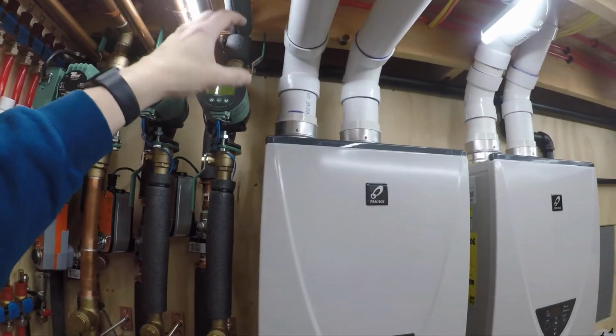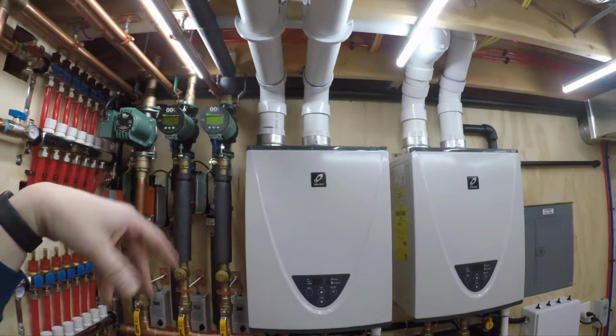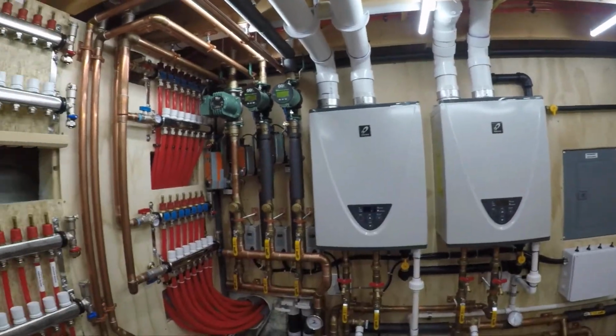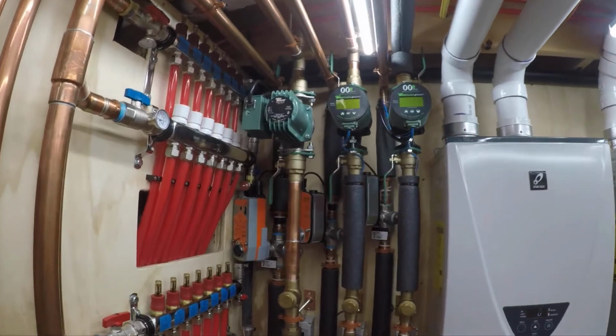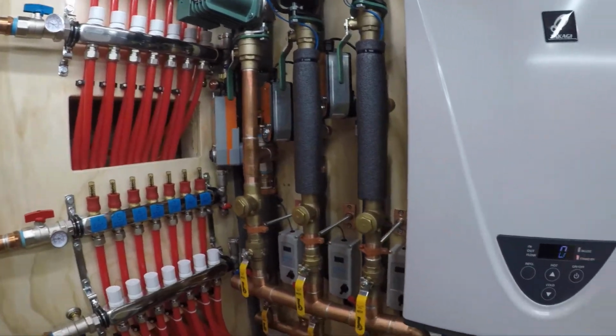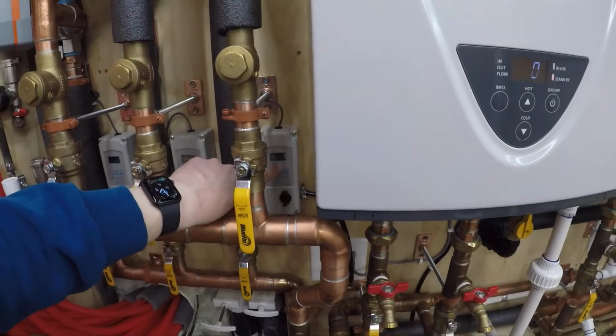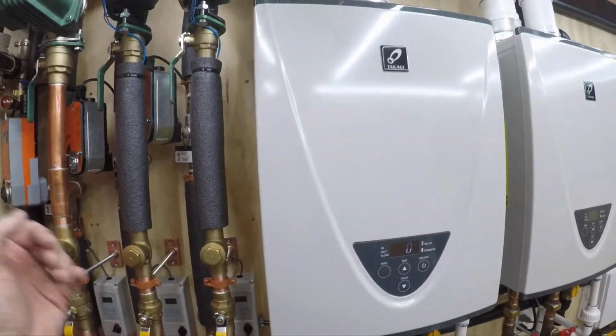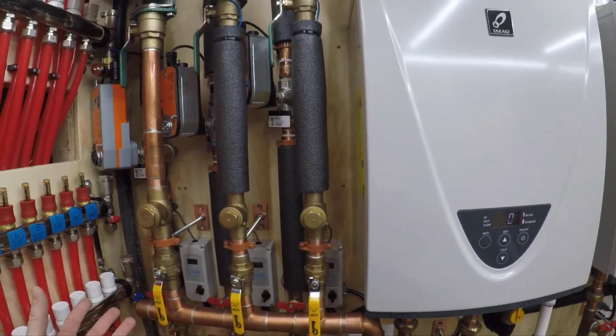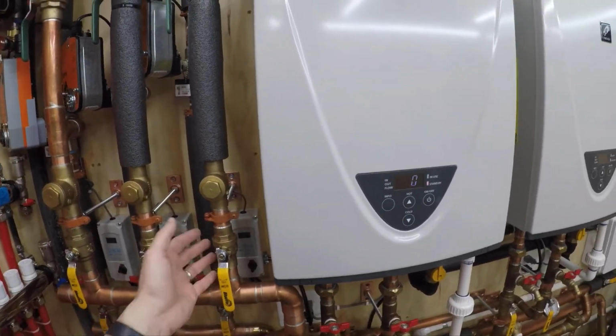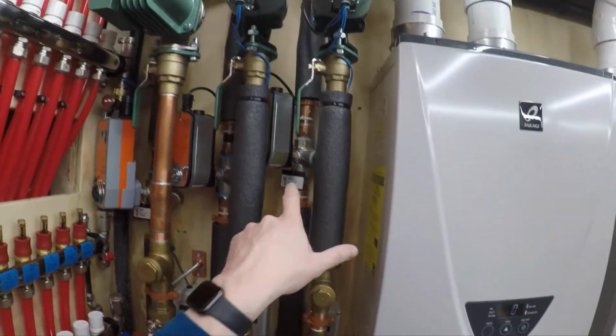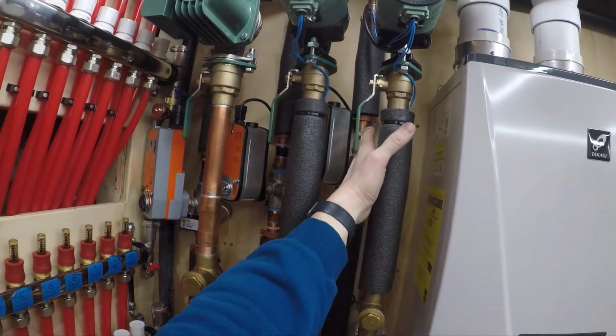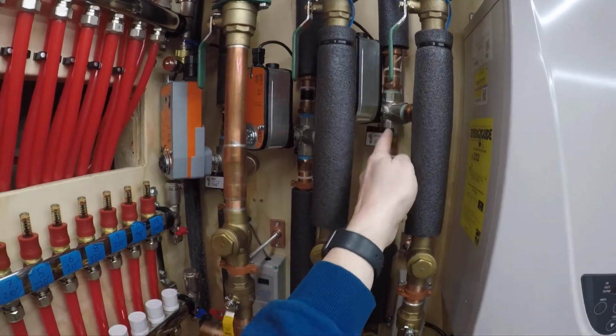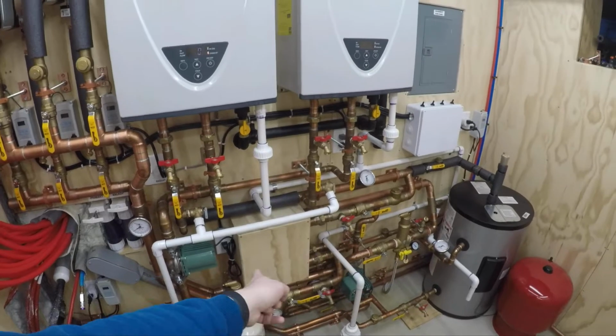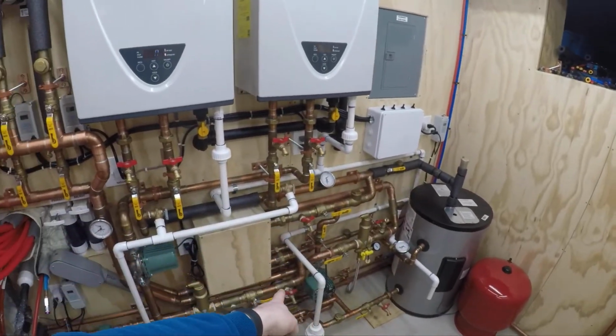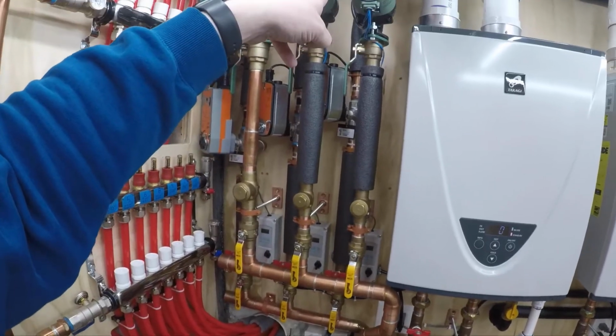And they will just continuously pump glycol through the floors. Okay? As that glycol cools down to whatever temperature I set on these aquastats, it gets to a certain point where it says, hey, I need more heat. The aquastat will then energize, and it does two things. It opens up this three-way valve and allows the glycol to now go straight through and down and through the return, which I'll show you, pick up more heat and come back out the loop that we just made and back to the supply. So it'll do that.